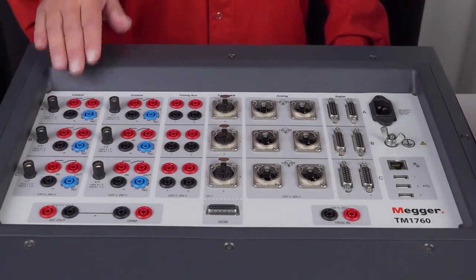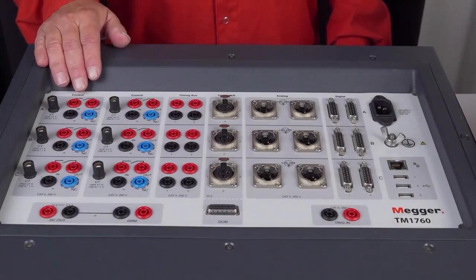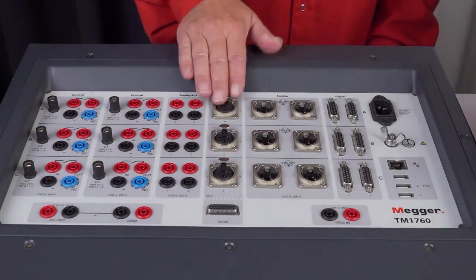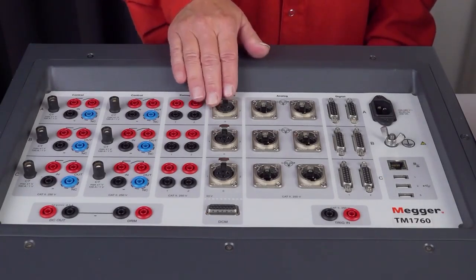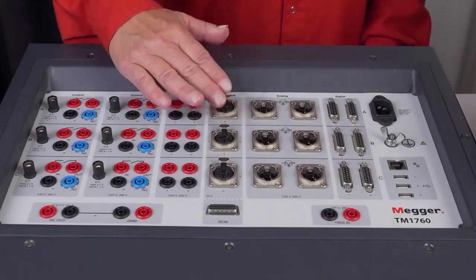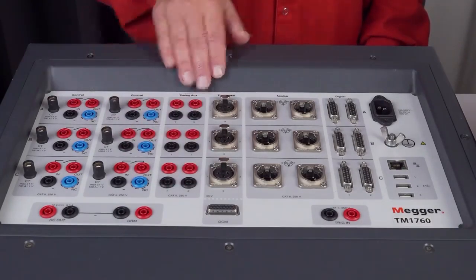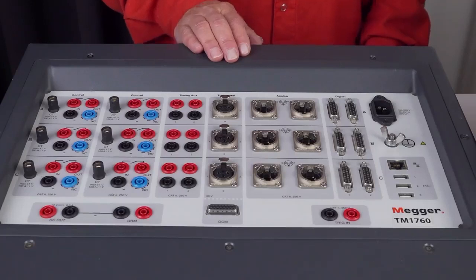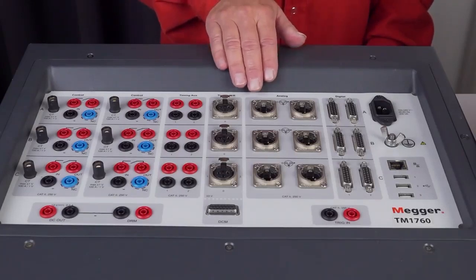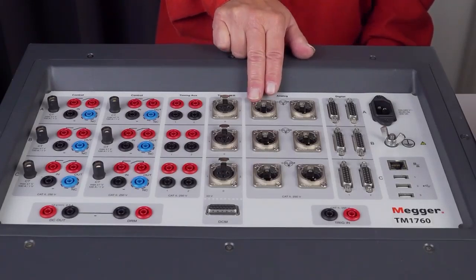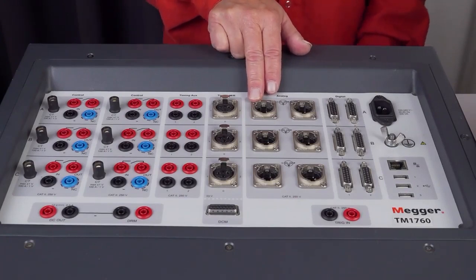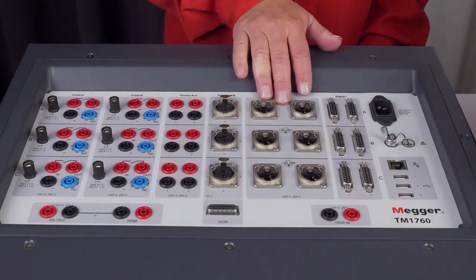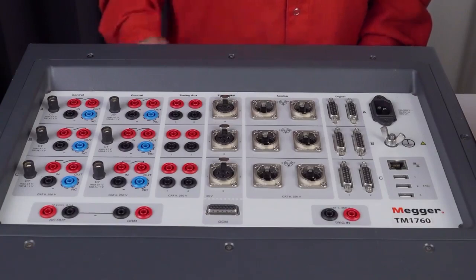It's measuring coil current at the same time and also automatically the auxiliary contacts in the circuit. We are going to measure timing, as I mentioned, with the timing channel. We're only going to use the three channels. This instrument has 6. And we're going to measure analog motion. And we're going to use the analog channel, which is flexible also for other analog measurements. And this instrument has 6 channels, but we're only going to use 1.